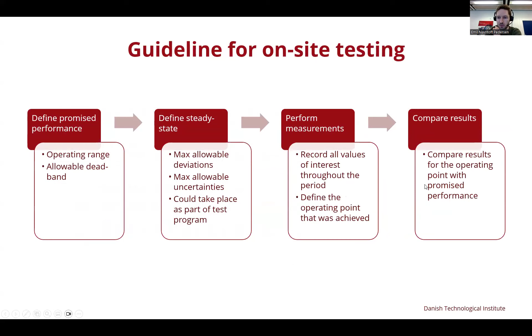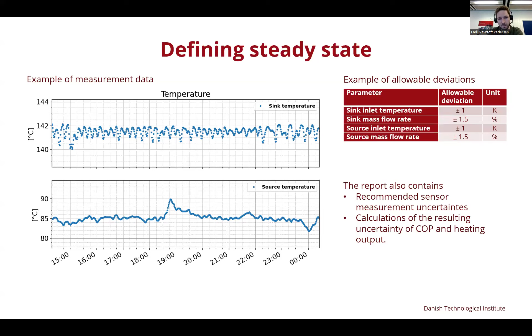The report also contains recommended sensor measurement uncertainties. So what precision should your sensors have? And these are based on industry standards related to heat pump testing. And it also includes calculations of what these uncertainties mean for the resulting COP. So if you have a given sensor uncertainty, how will that affect the uncertainty of your calculation of the COP and also the heating output of the heat pump? So you could calculate backwards from that and find what sensor accuracy you want if you need a certain uncertainty of your COP.